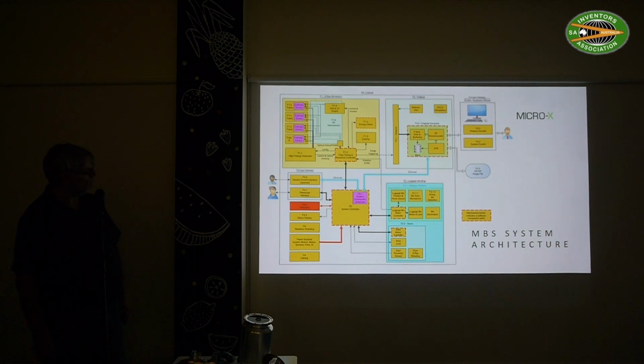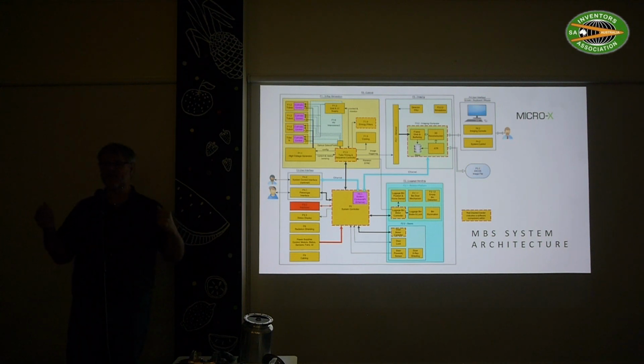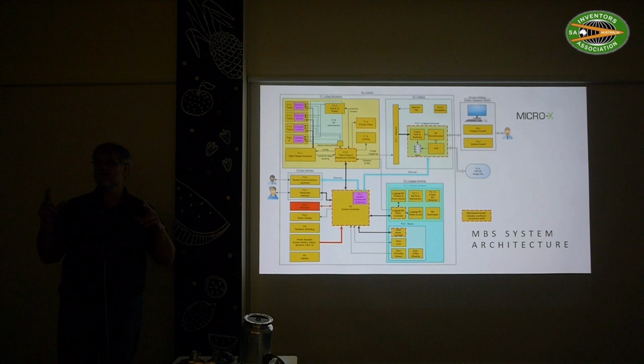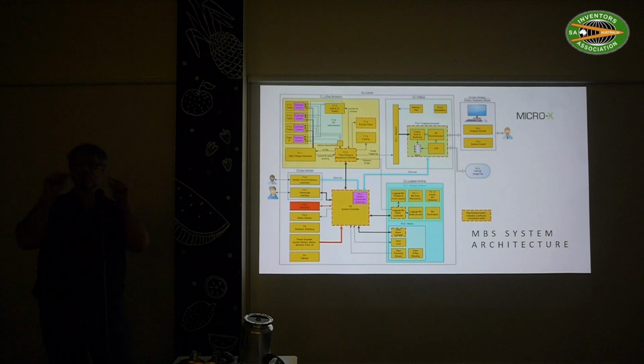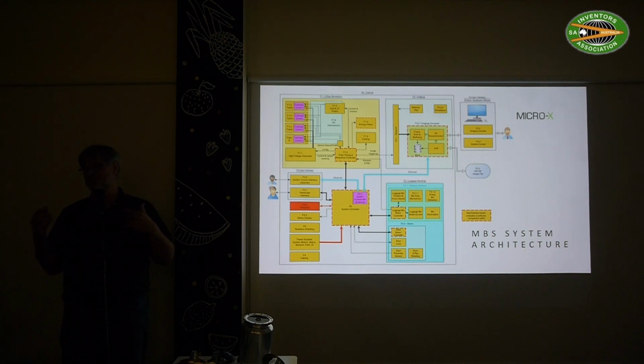And then the system computer on the other side has some displays, and there is some special checking for making sure that everything is in place. Is the door closed? Is the bin operating at the right speed? And all these safety checks before we are able to activate the high voltage, because there are all these requirements we need to meet. Even down to the point of we need to turn on a little light that says X-rays are on. That's the requirement. And if the X-ray light fails, we need to stop.